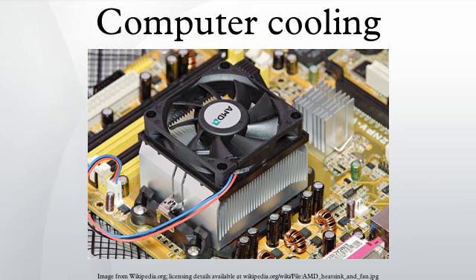Heat removal was critical. Liquid Freon refrigerant was circulated through piping embedded in vertical cooling bars in 12 columnar sections of the machine. Each of the 1662 printed circuit modules of the machine had a copper core and was clamped to the cooling bar. The system was designed to maintain the cases of integrated circuits at no more than 54 degrees Celsius, with Freon coolant circulating at 21 degrees Celsius. Final heat rejection was through a Freon-to-water heat exchanger. Piping, heat exchangers, and pumps for the cooling system were arranged in an upholstered bench seat around the outside of the base of the computer. About 20% of the machine's weight in operation was coolant.